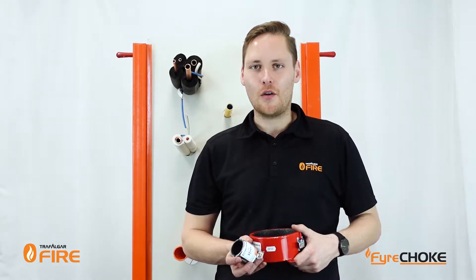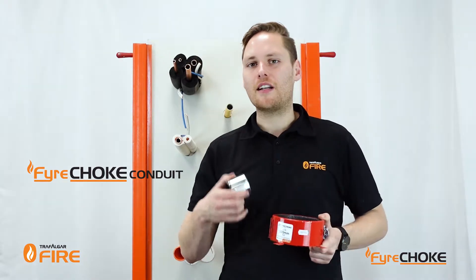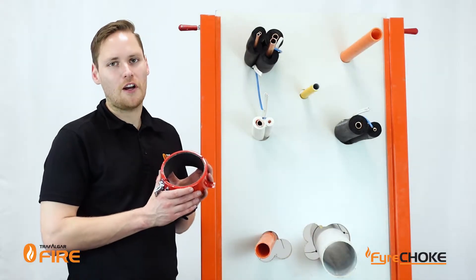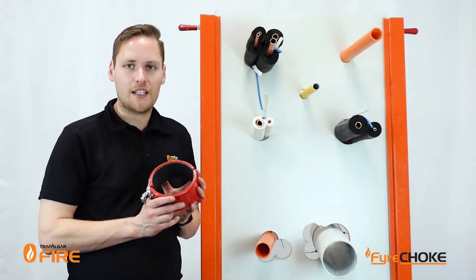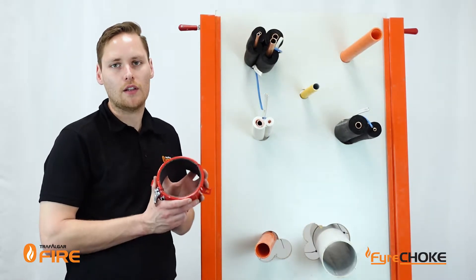G'day guys, in today's video I'll be showing you how to install our FyreCHOKE Premium Hinge Retrofit Collars and our FyreCHOKE Conduit Collars around some typical services and show you the tips and tricks about how to get compliance on site. Now with all passive fire materials you do need to make sure that they're tested for exactly what you're trying to do with them. So the first step should be to check out the product manual on tfire.com.au to see the range of approvals for walls and floors with our collar systems.